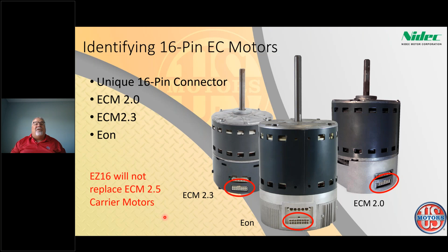So that's our identification features, as we talked about. The nice thing about this motor is it uses the exact same wiring as the OEM, so there's no changes in the wiring setup. You have adjustable airflow after the installation, so you'll be able to actually dial this motor in. It does have a multi-horsepower function I'll show you here in a second. And this little box gets mounted remotely, somewhere inside the cabinet, so you can adjust the airflow to dial that in. First thing we're going to look at is that we did get a generic profile into this motor, and that is where our engineering came in.